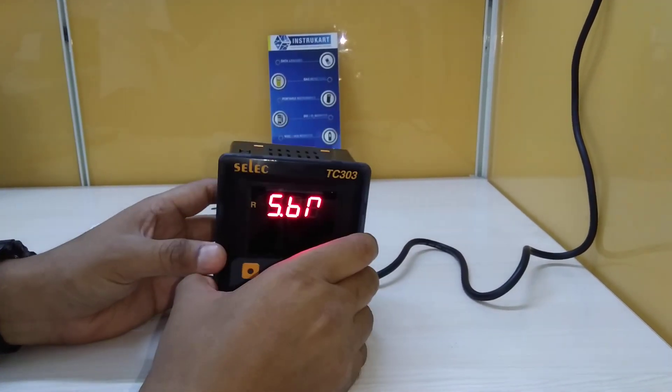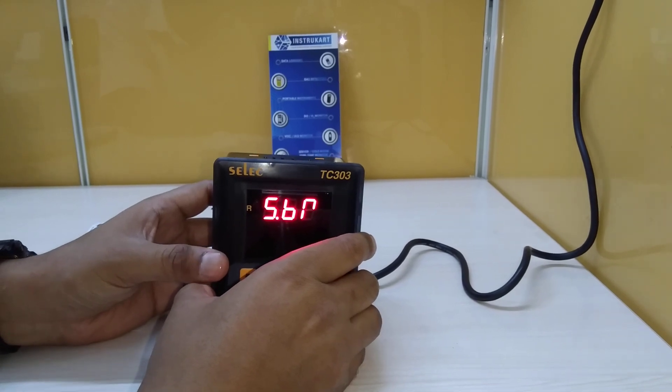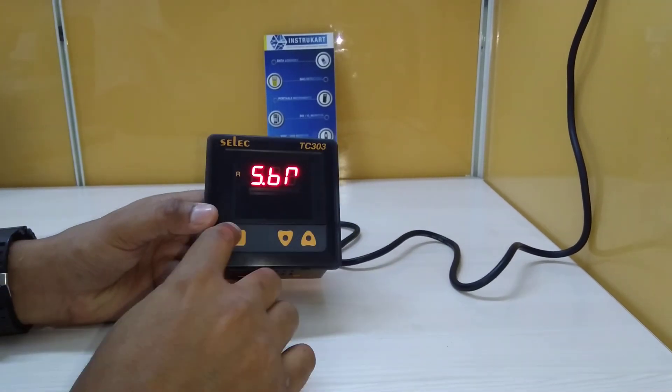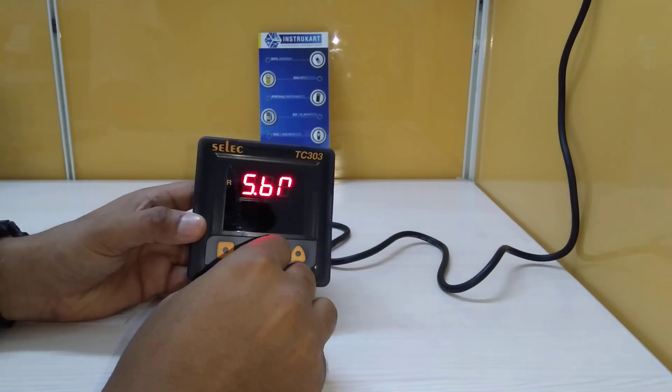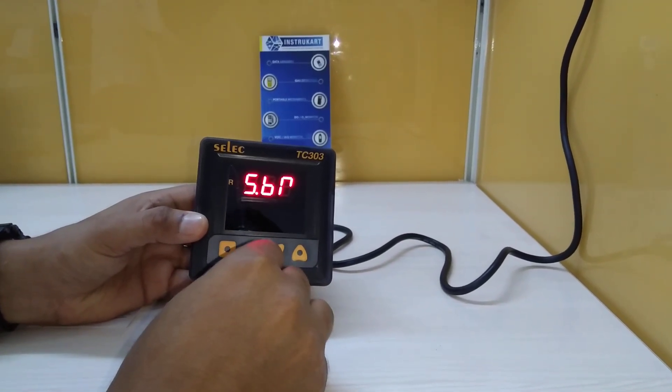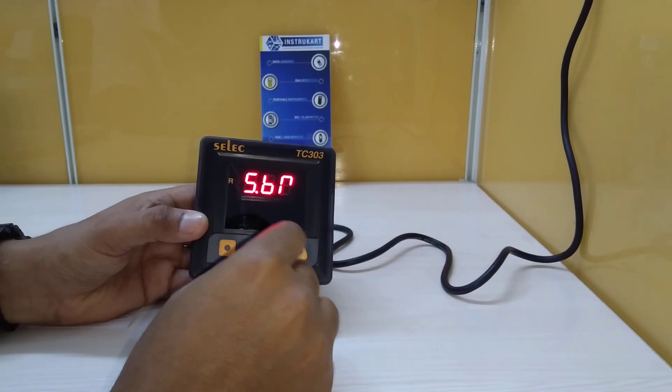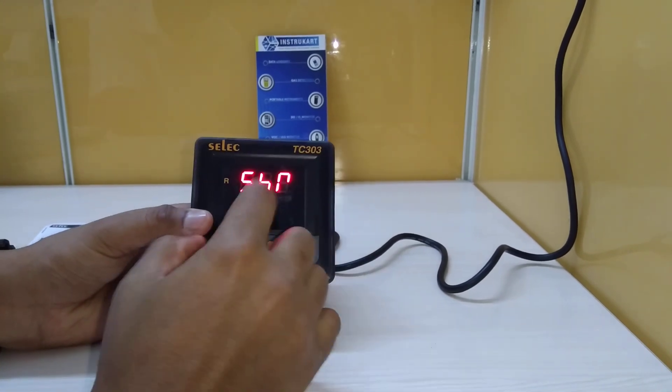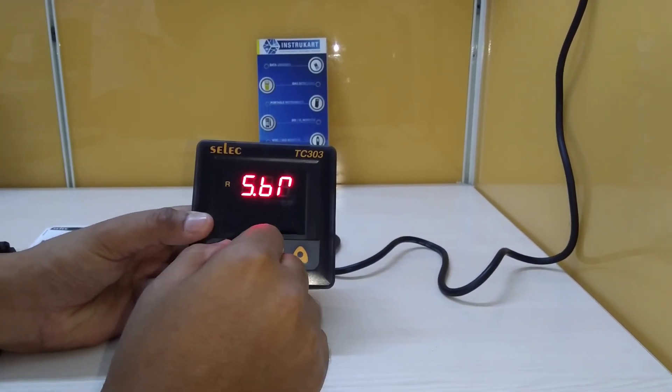It has three keys for digital setting and can take input signals from thermocouples JKT RS and also RTD PT-100. The temperature unit is selectable between Fahrenheit and Celsius.